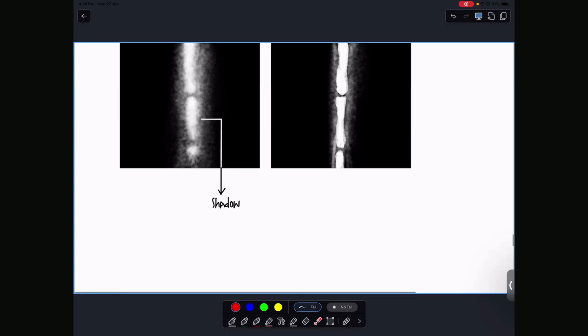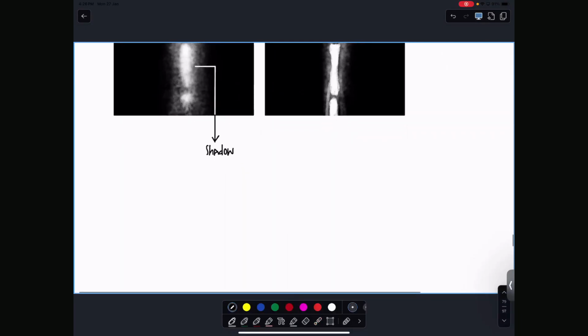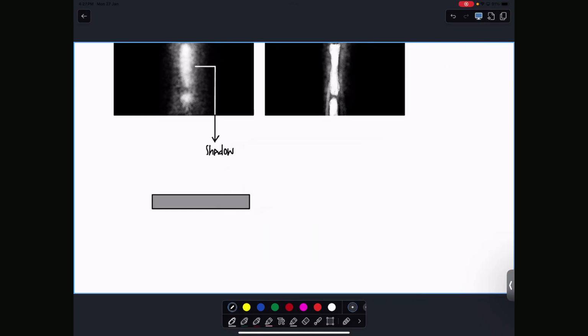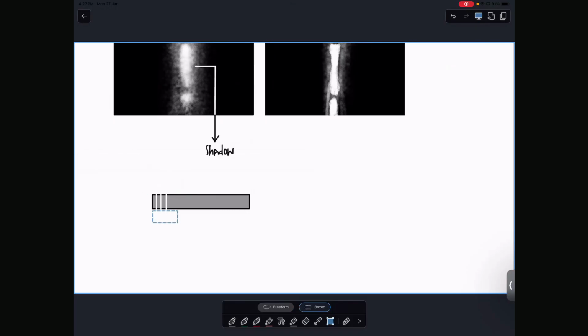The collimator. So the collimator is this device that we've seen last class. It's this lead filter. Inside there are millions of very small lines, and these lines that you see are all parallel to each other. Having these parallel lines ensures that if there are X-rays out there, they'll only travel in a straight line before they reach the plate, right? So yeah, I'll show you, don't worry.